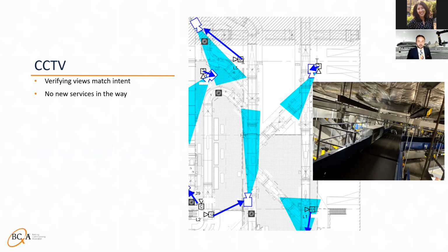Cameras are often placed in drawings, but the drawings may not show all of the services that are in the way. In this one, for example, you'll see a duct that's over top of the system, but not shown on the drawings. Sometimes you'll put cameras out in the field and someone will put a duct right in the view because they're busy doing their part. So you'll want to check once everything's done that CCTV locations match what was intended in the design.